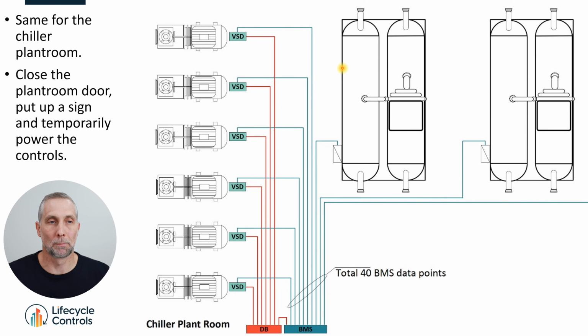Same thing for the chiller plant room. Lock the door, put a big sign on the door, temporary commissioning underway, power up the BMS panel temporarily, do some stuff in here. I think it's a bit more difficult with the chiller plant room because you need a lot of containment, electrical containment to be installed all around you by others. Maybe this wouldn't work so well in the main plant rooms. There's only one chiller plant room, one boiler plant room, one cooling tower plant room. If you didn't get much of this done, so what? You've got 50 air handling units that you can do.